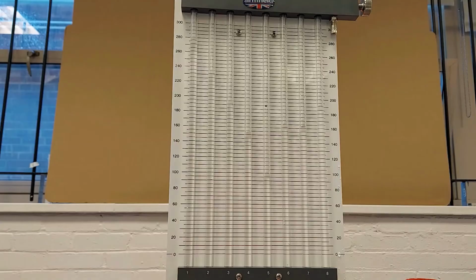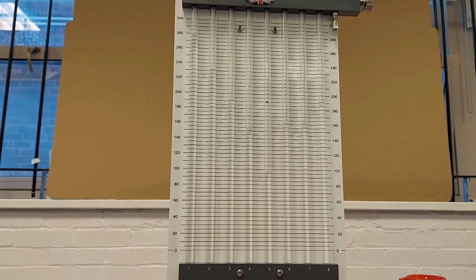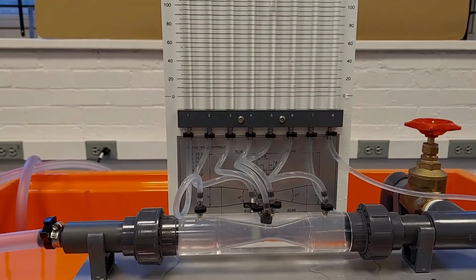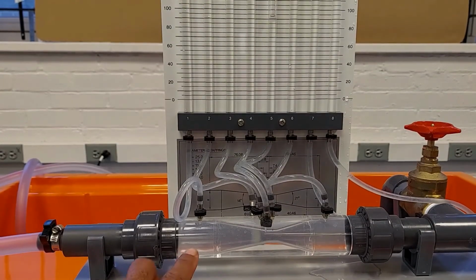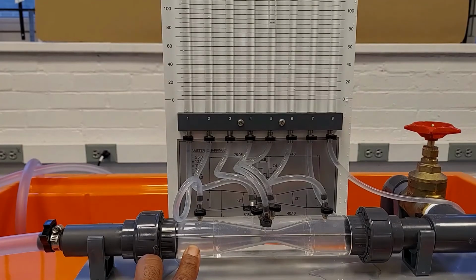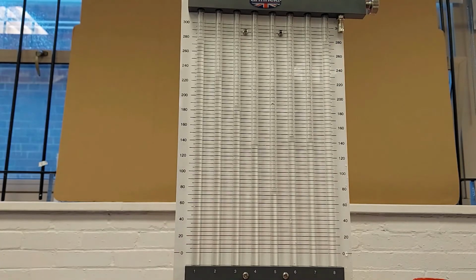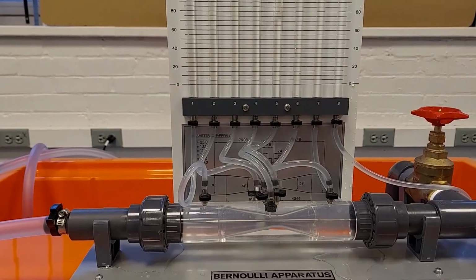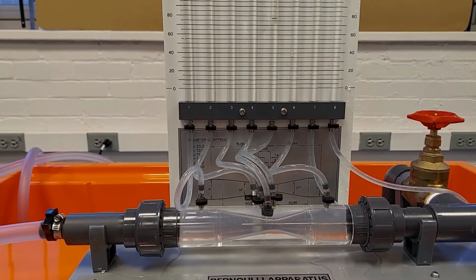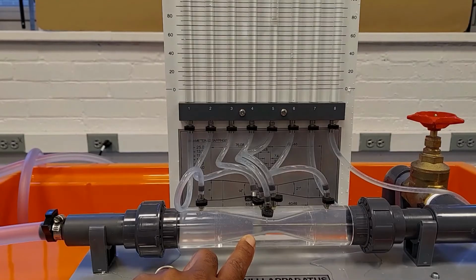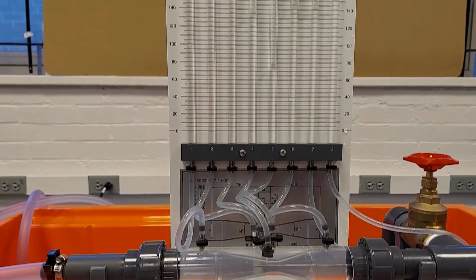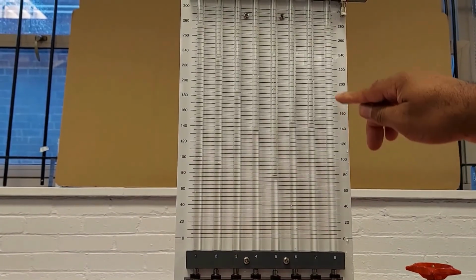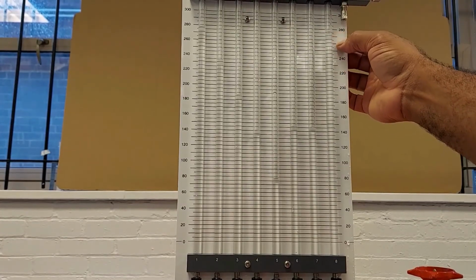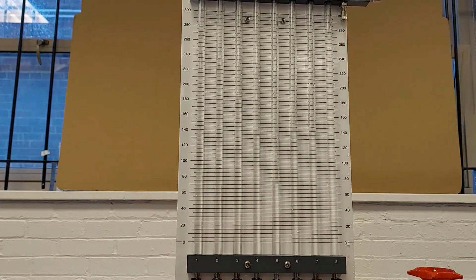Next, what we would do is to adjust our probe to H1, which would give us our total head reading, 275. Then we would adjust our probe to H2, give the system some time, then take readings again for H8, and we're at 275.